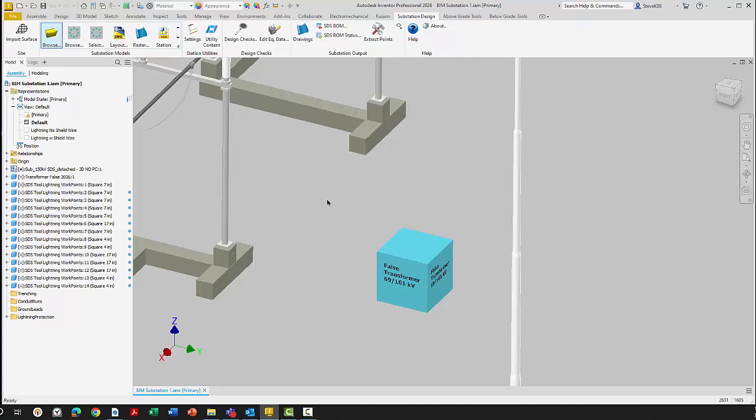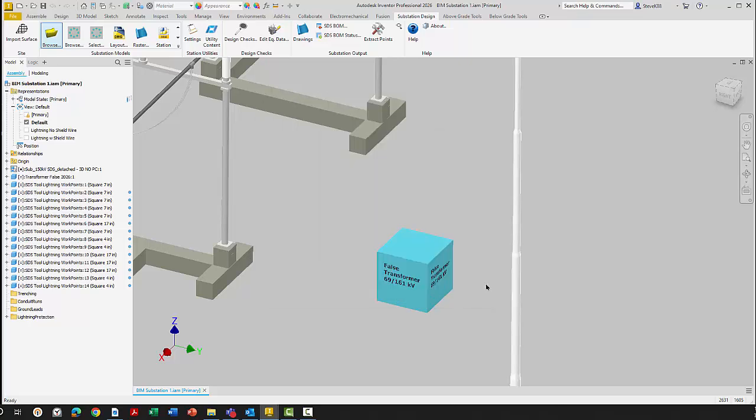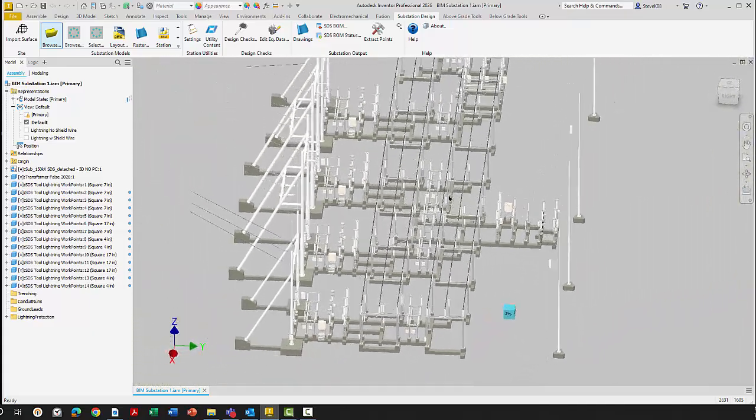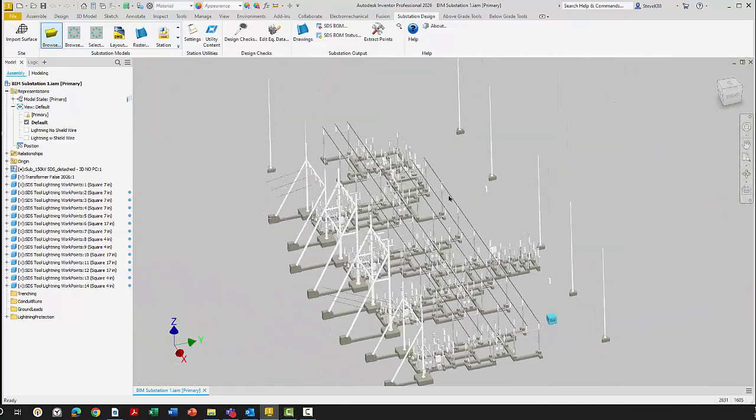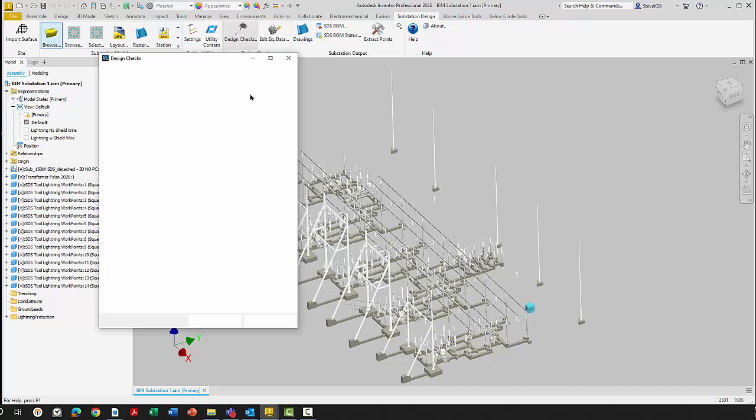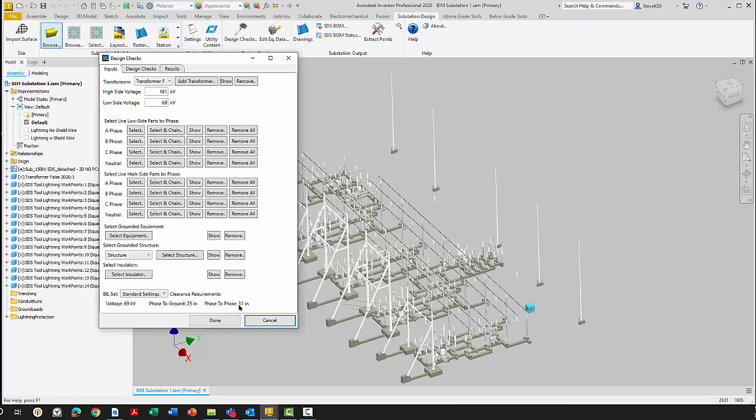I can also view that from equipment design data. I can open that up and I can see that transformer and I have the settings here. I can see it from both ends. With that transformer in there, when we start up our substation design tool, we can review this voltage setting. Voltage is 69 kV. Spacing is 25 to 31. And that is set in the database. That's configurable values in the database. So we have everything set and now we can run our design checks.